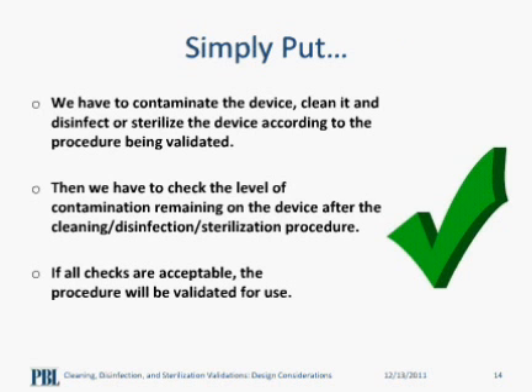I have just gone over quite a bit of material, and it may still be a little confusing, but simply put, to validate the reprocessing procedure, we have to contaminate the device, clean it, and disinfect or sterilize the device according to the procedure being validated. Then we have to check the level of contamination remaining on the device after the cleaning, disinfection, and sterilization procedure. If all checks are acceptable, the procedure will be validated for use. This whole validation procedure doesn't look so confusing now, right?